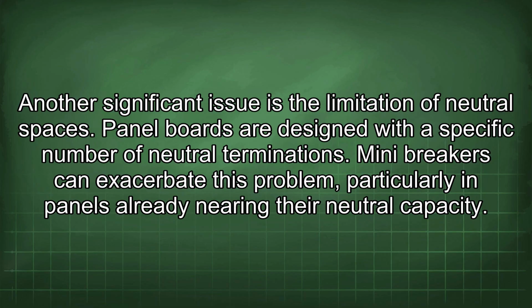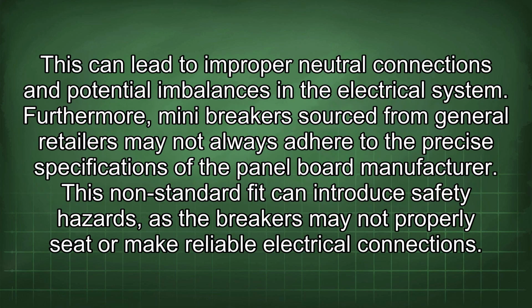Another significant issue is the limitation of neutral spaces. Panel boards are designed with a specific number of neutral terminations. Mini breakers can exacerbate this problem, particularly in panels already nearing their neutral capacity. This can lead to improper neutral connections and potential imbalances in the electrical system. Furthermore, mini breakers sourced from general retailers may not always adhere to the precise specifications of the panel board manufacturer. This non-standard fit can introduce safety hazards, as the breakers may not properly seat or make reliable electrical connections.